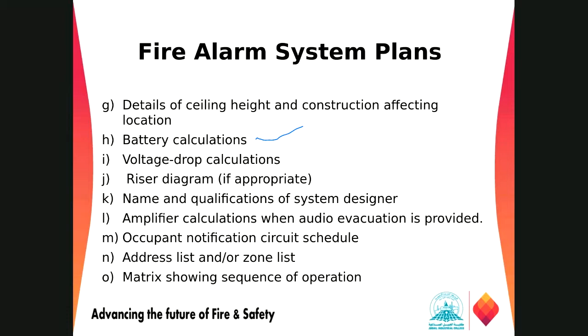We have the primary supply and we have the secondary supply. Secondary supply is the battery connection. In case the primary supply goes off, the battery supply will be activated, and it will power the fire alarm control panel. For the devices, while the devices are not working, it will supply some load. And while your devices are working, right, the smoke detector activated, your audible sounder, the horn strobe started, and there is no power at those moments, the battery should supply the power for those requirements for at least some minutes or some hours as per NFPA 72. This is the reason for that.